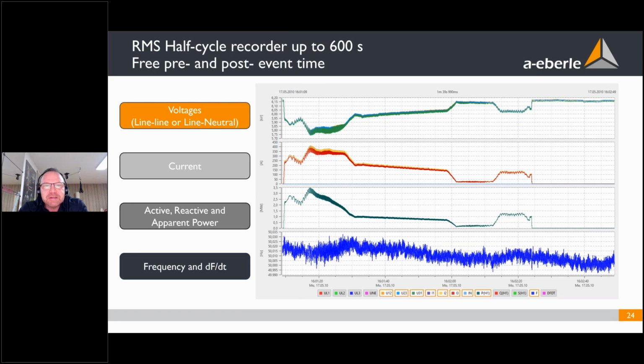Another big feature of our devices is that we can have really long disturbance records. Here is a big 4 megawatt motor at an industry customer, and when a big 4 megawatt motor starts, it takes a long time. This plot covers about 1 minute and 40 seconds, so 100 seconds the 4 megawatt motor needs to start. We not only measure the voltage dip and the current, we also have the real power, apparent power and reactive power on the basis of 10 milliseconds. Even the frequency or frequency change is done on the basis of 10 milliseconds. This is unique. You get a really long record, and not only voltage and current like most of the competition, you also get all power and frequency data on the basis of half cycles.